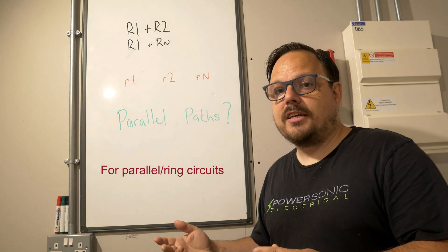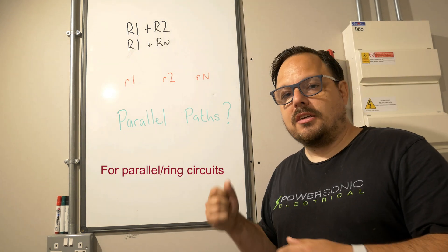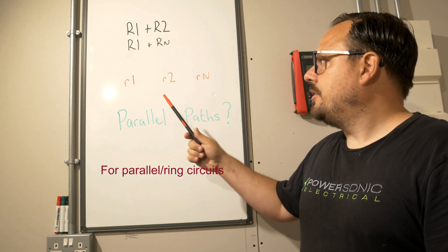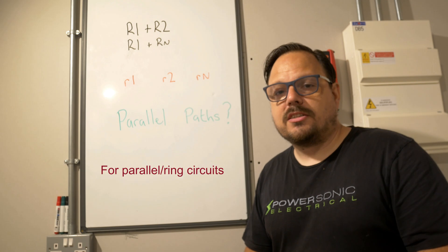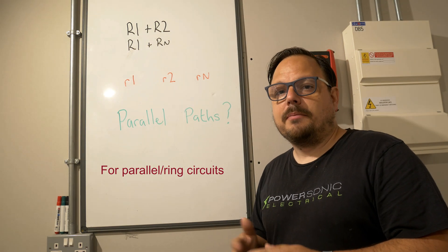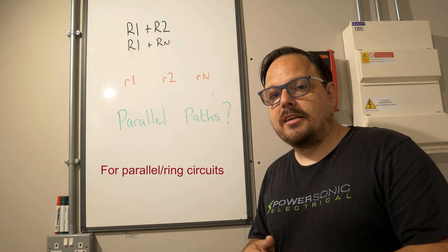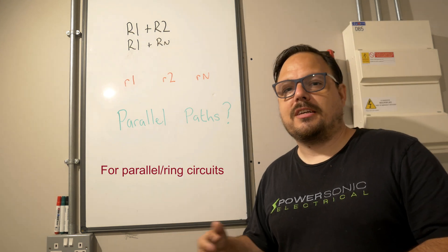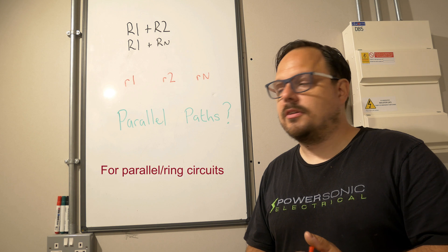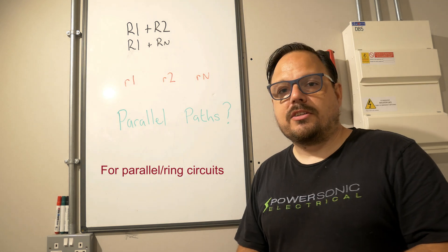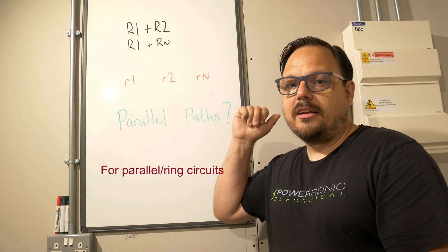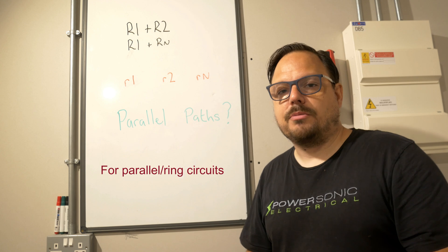If it were three phase you would obviously have three line conductors to measure through as well. For ring final circuits especially, these are really important measurements because they help build a picture of continuity through those conductors as you step through the test sequence. On this radial circuit we've got the socket just down there as the end of line, so we know that's the final point, and the origin is here in this distribution board behind me.